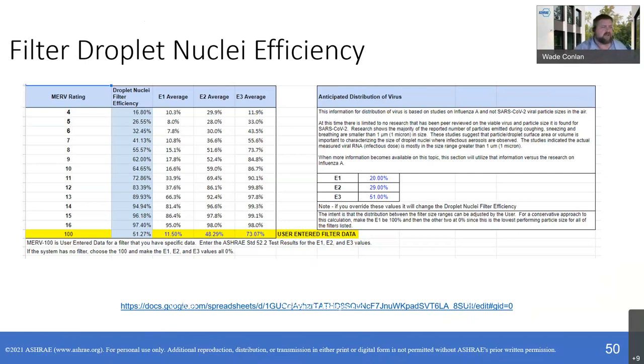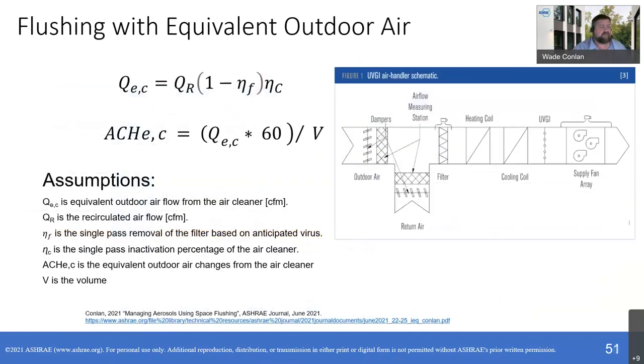Next slide, please. And then that information, that's for the filter. Now we need to talk about the air cleaner, the UVGI. The filter and the UV essentially are filters in series, right? So the airflow from the air cleaner is really the recirculated airflow times what the filter didn't catch times the efficiency of what the air cleaner is doing.